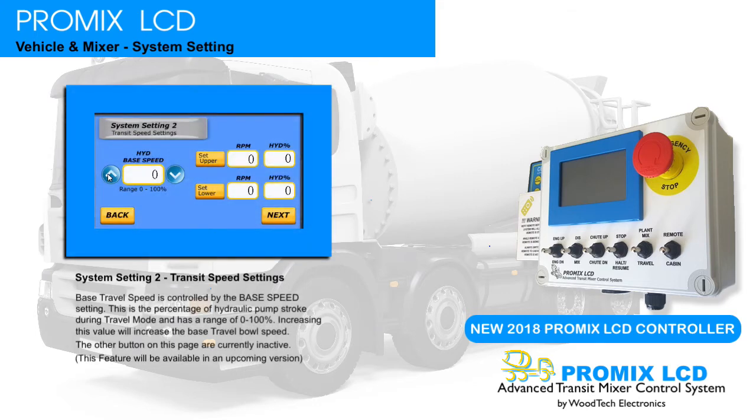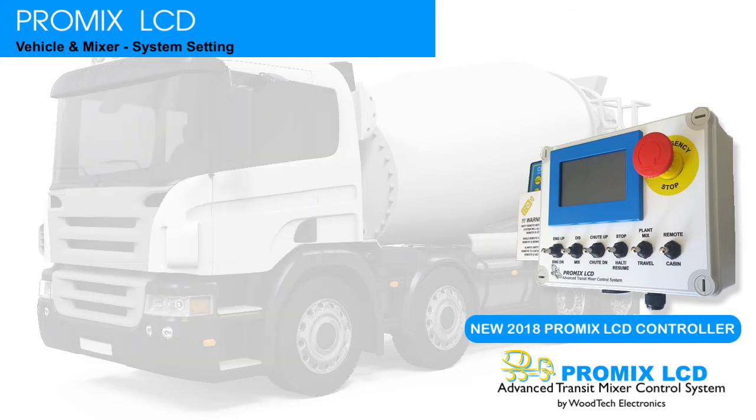System Settings 2, Transit Speed Settings. Base travel speed is controlled by the base speed setting. This is the percentage of hydraulic pump stroke during travel mode and has a range of 0 to 100%. Increasing this value will increase the base travel bowl speed. The other buttons on this page are currently inactive. This feature will be available in an upcoming version.